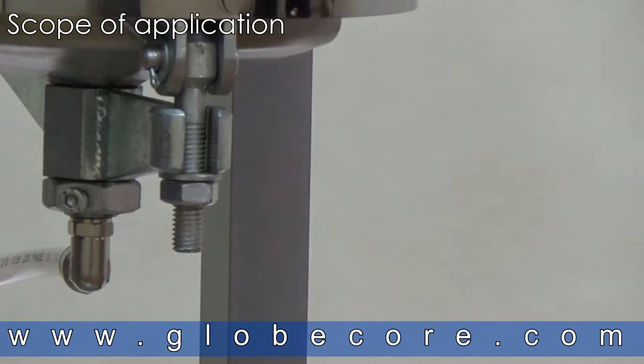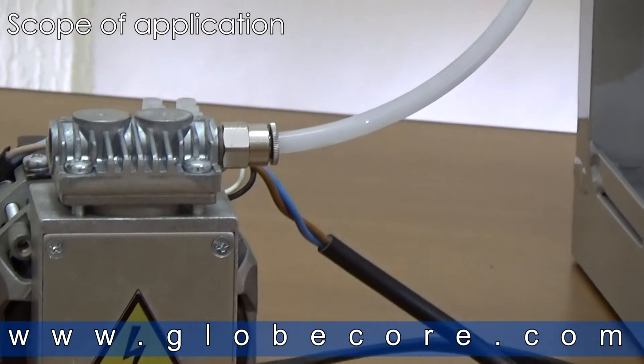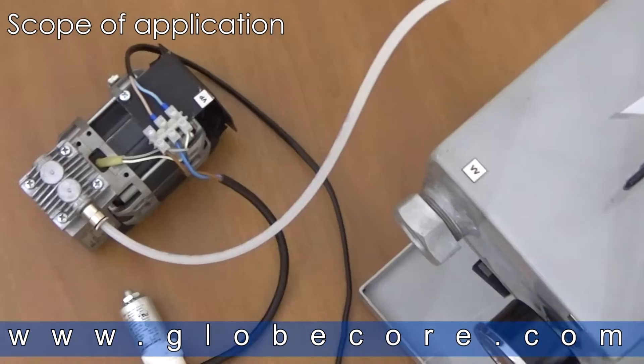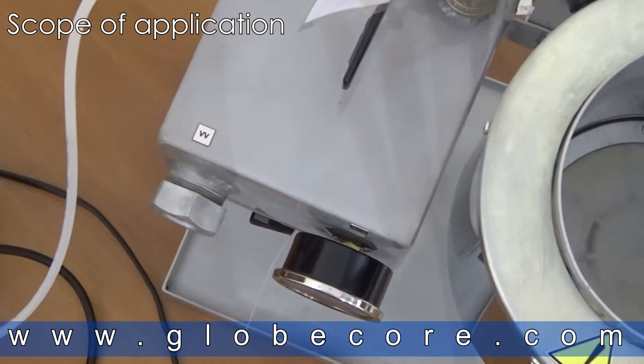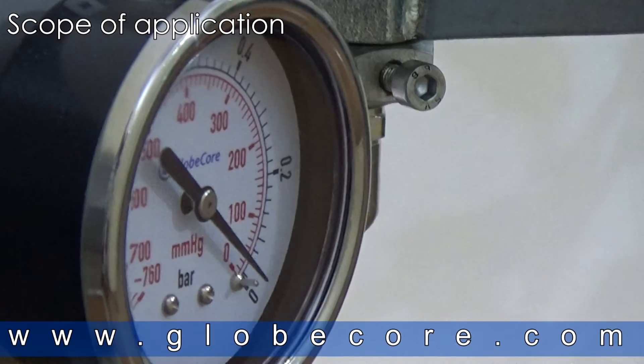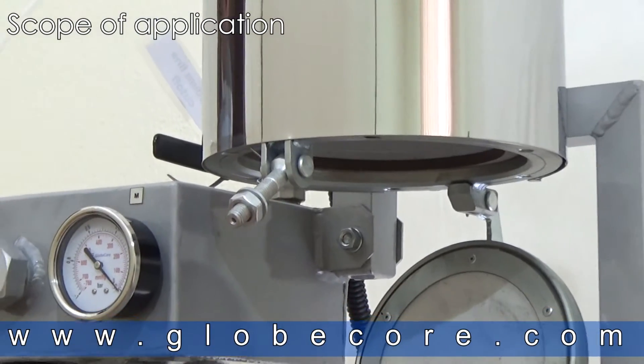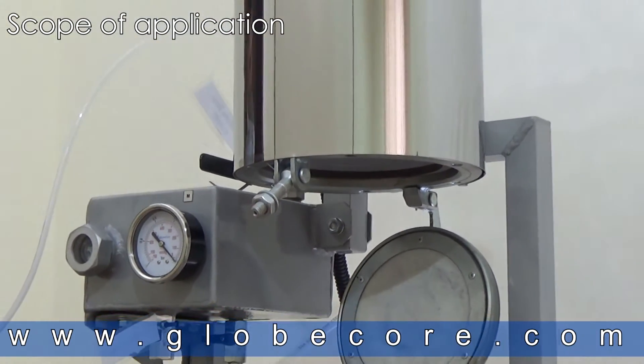SCOPE OF APPLICATION. The GlobeCore Vacuum Regeneration Laboratory Unit is designed for the regeneration and lightening of dielectric insulating oil, turbine oil, and industrial mineral oils. The viscosity of the regenerated product at 50 degrees Celsius must not exceed 70 centistokes.